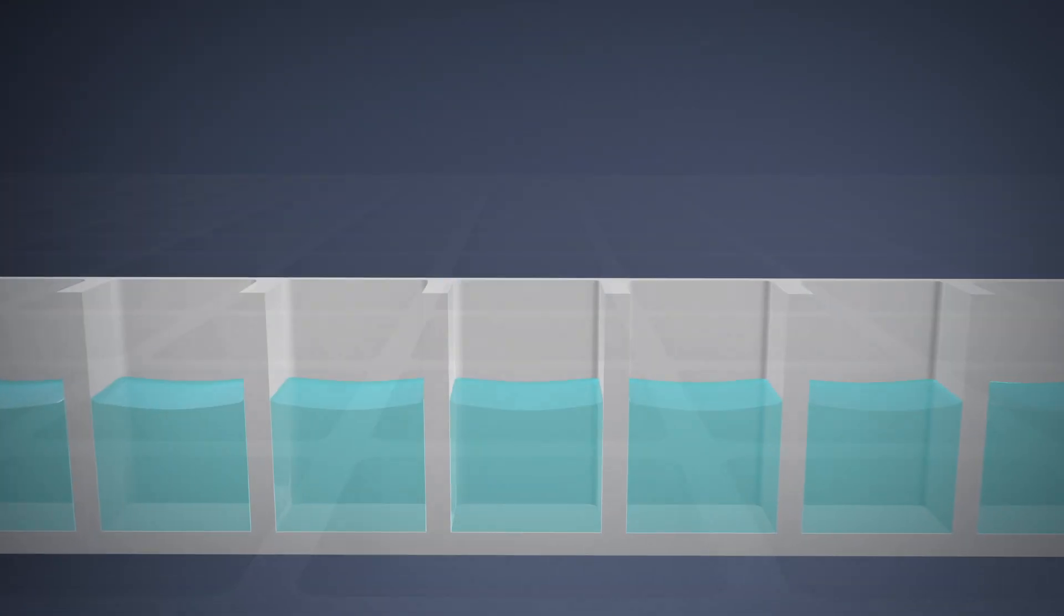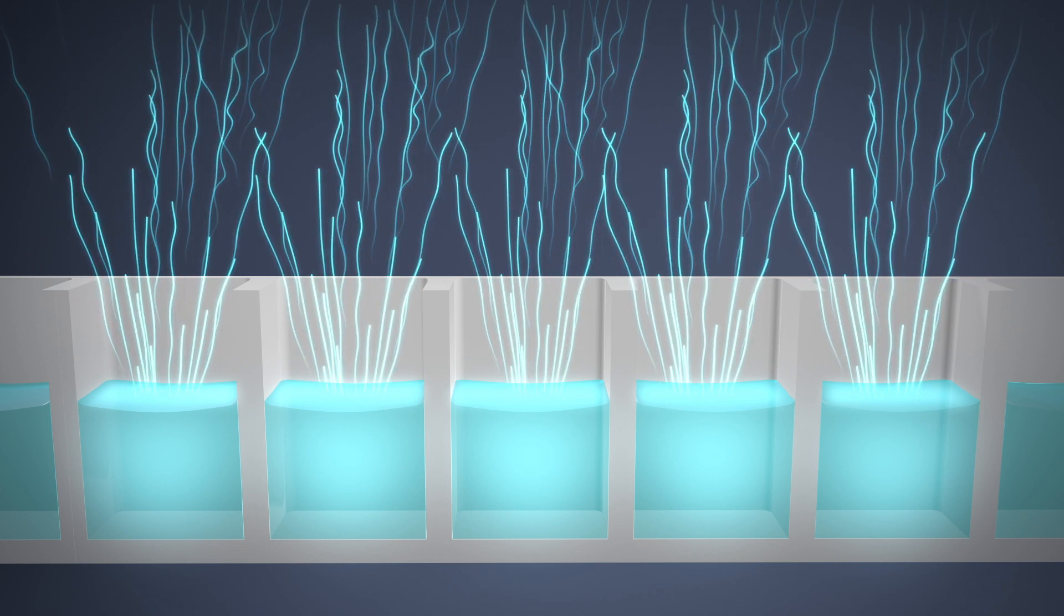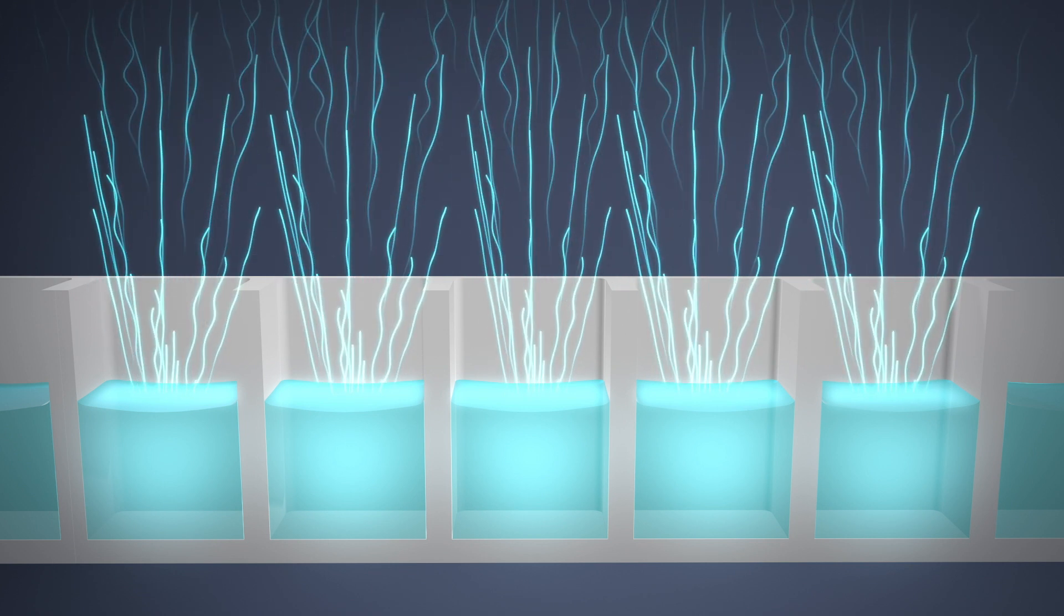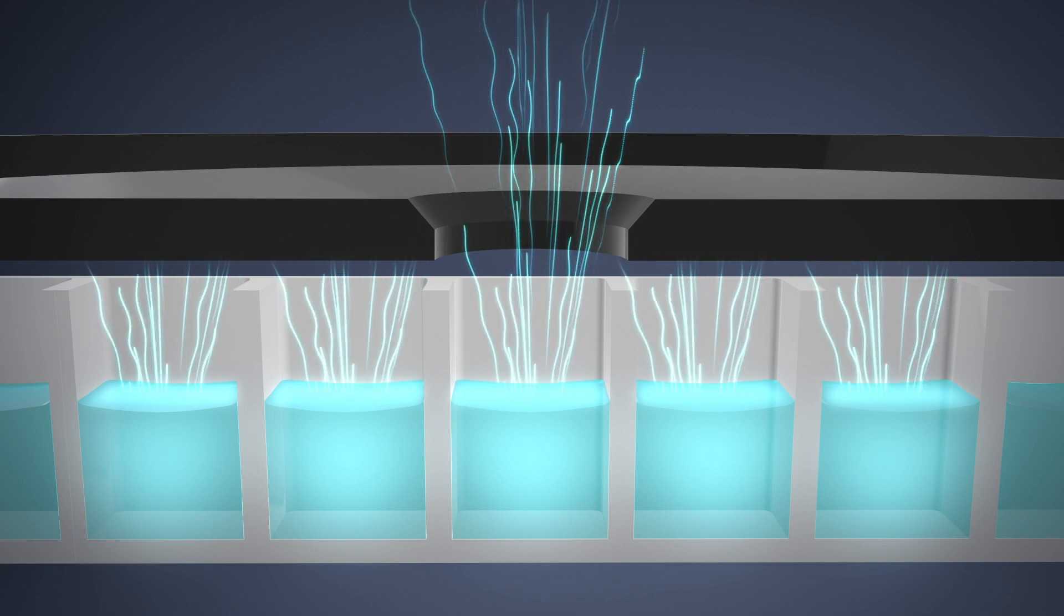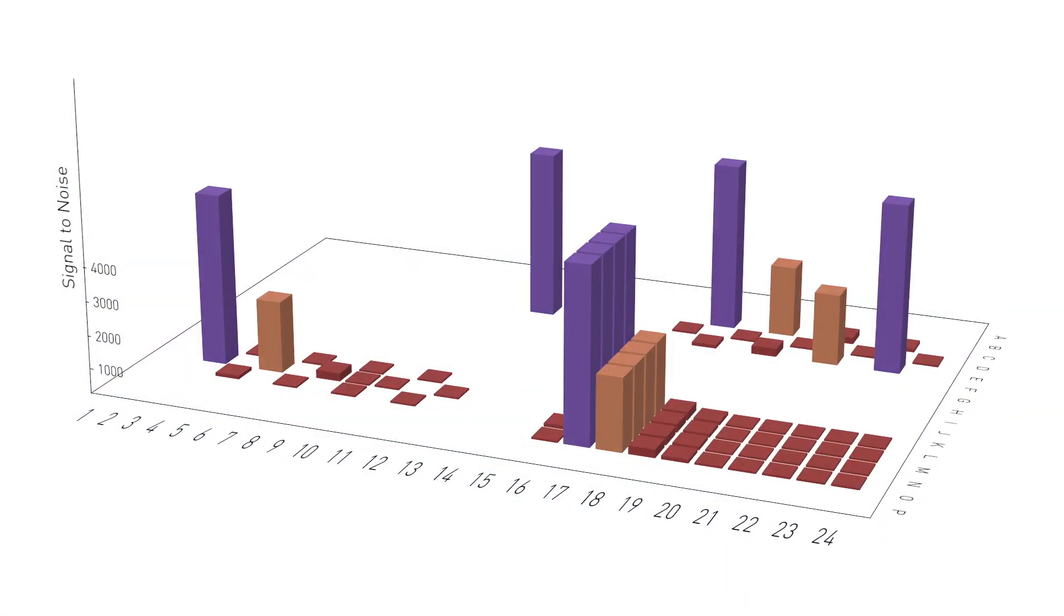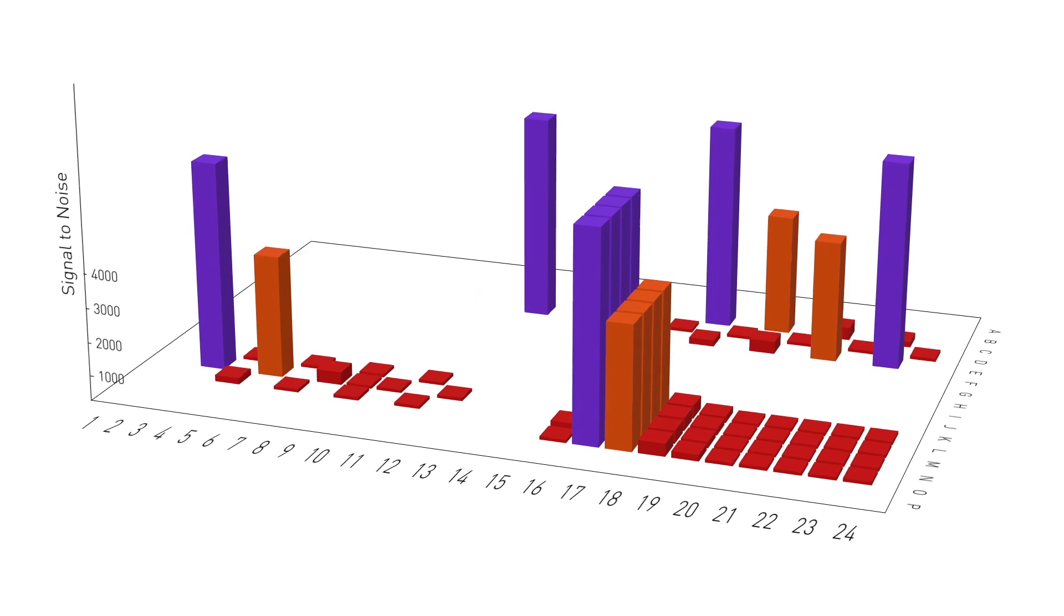Data quality in these assays can be affected by microplate designs, which allow light from neighboring wells to cross over between one another. Through crosstalk correction, apertures are automatically used to reduce noise from adjacent microplate wells, thus improving the signal-to-blank ratio.